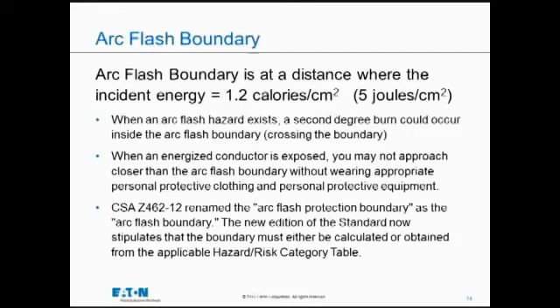And they used to say arc flash protection boundary, but that word protection has been taken out in the last version of the Canadian Best Practice Guide, the Z462 standard. That's the bottom paragraph. So the concern is, do you get yourself into trouble, or have you crossed the arc flash boundary? That's the moment at which you kick in the arc flash hazard.